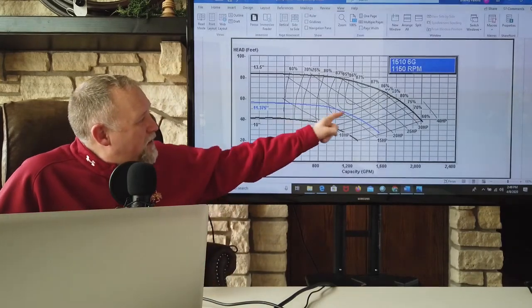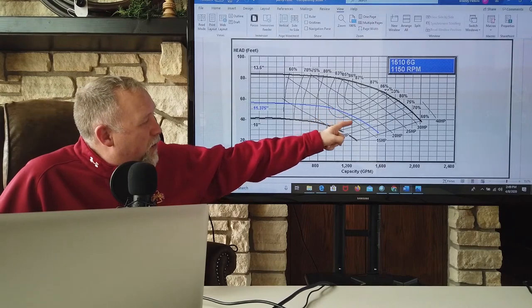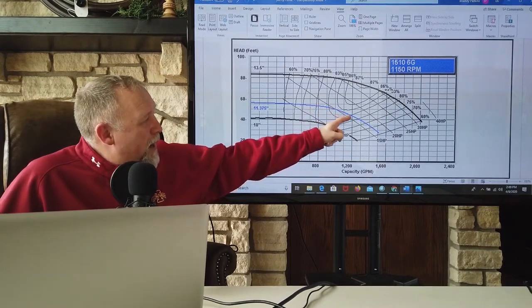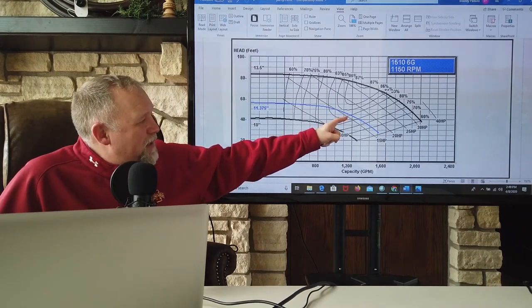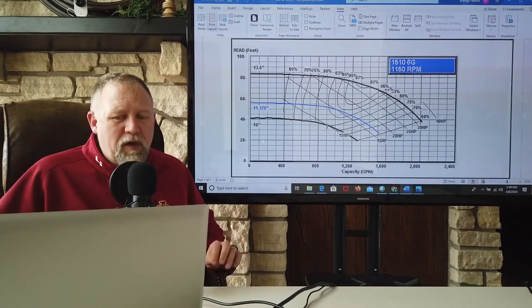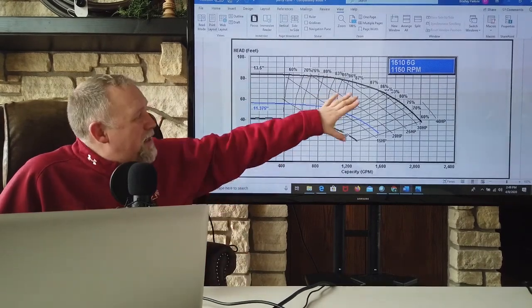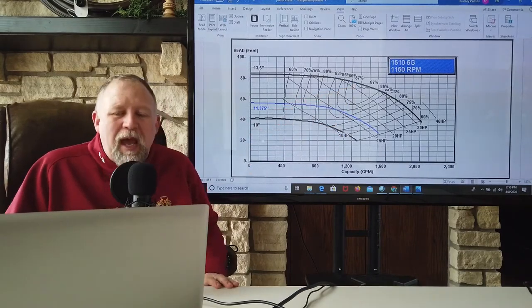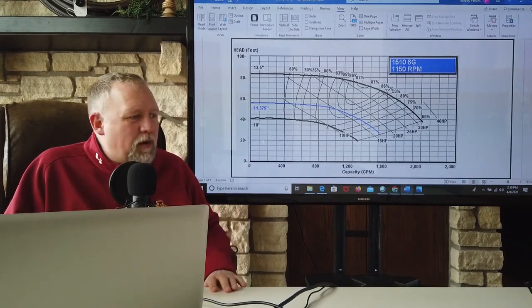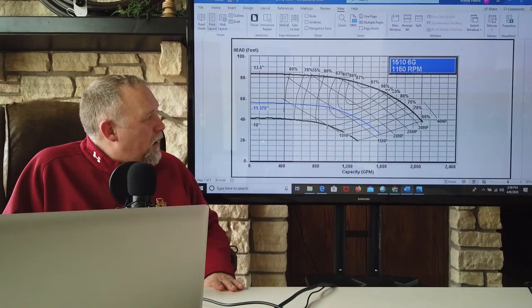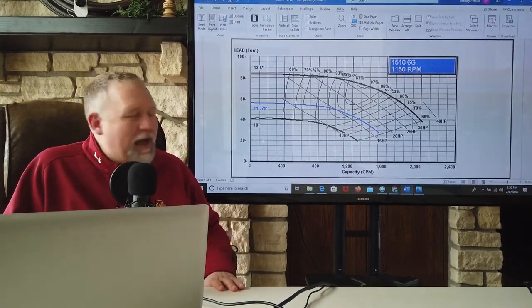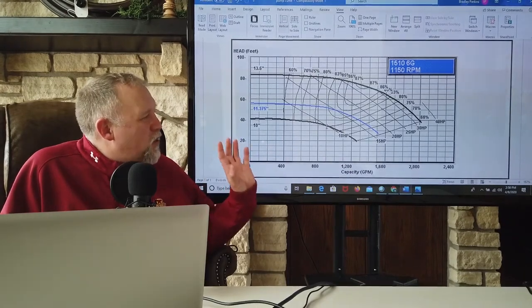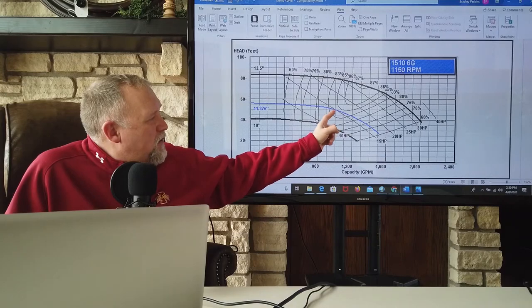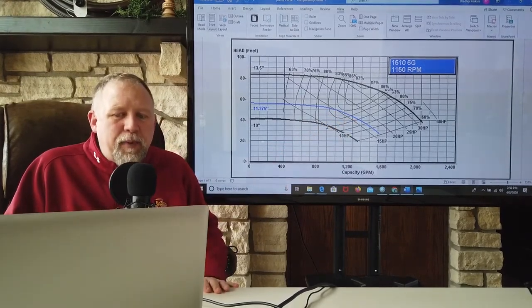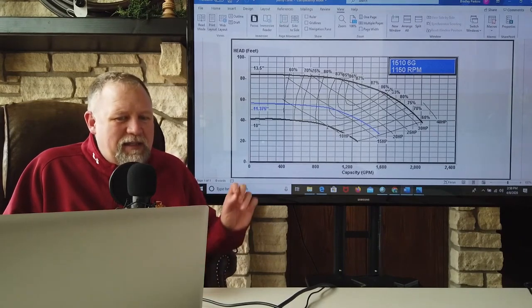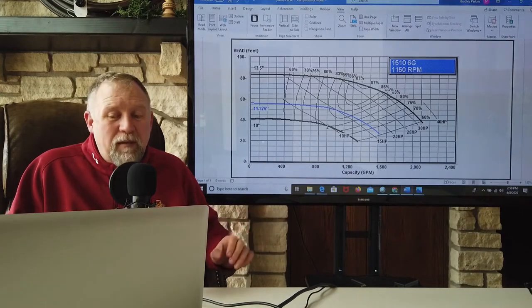However, notice that as we ride the pump curve to the right, we're going to consume more and more power, and we could potentially be in a situation where we overload that motor. That motor is going to try to spin at whatever speed it's designed for. This one happens to be 1150 RPM. It's going to spin at whatever speed it's designed for and consume as much power as it needs to do that. If you need a little review on motor theory, talk to Jimmy in electrical class, right? But it's going to spin and draw as much power as it needs. If it goes too far past here, it could easily burn up the motor that is attached to it, and that's what we refer to as smoking the motor.